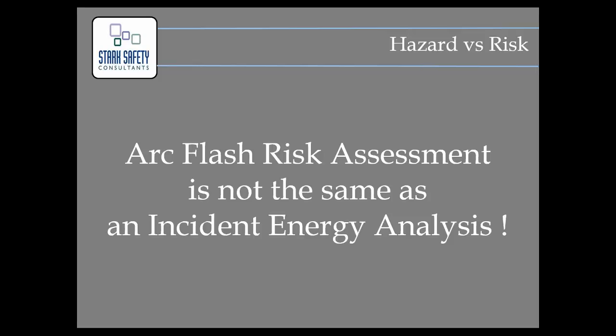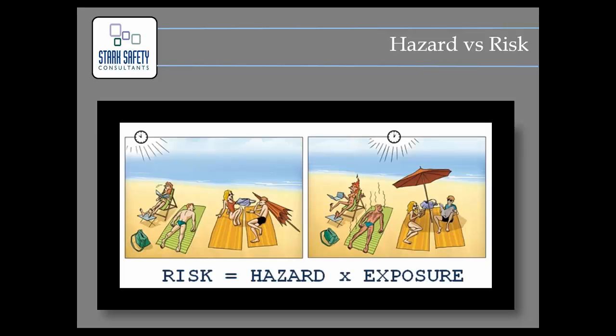two things. A lot of you in this group said you've already had an arc flash analysis completed. Have you done the arc flash risk assessment or just the incident energy analysis? You can go to the definition section in the NFPA 70E, which now says the incident energy analysis is just a component of the overall arc flash risk assessment. So if you've had an arc flash hazard assessment, that doesn't necessarily mean you've completed the arc flash risk assessment. The risk component needs to be included.